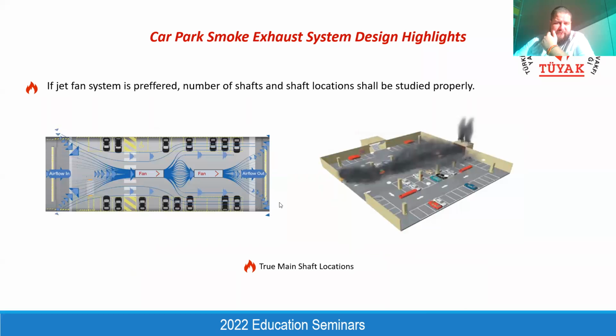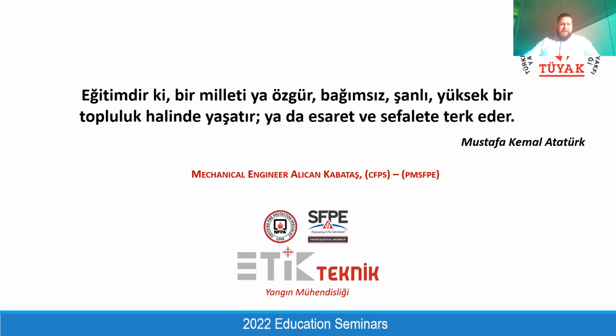And you can see the shaft locations here. They are located on opposite walls, so that when a fire incident occurs, the jet fans take the fresh air from one side and throw the smoke to the other side, and it is extracted to the outside of the building by axial fans located within the shafts. And that's all from my side to you, the architects, regarding the mechanical design.